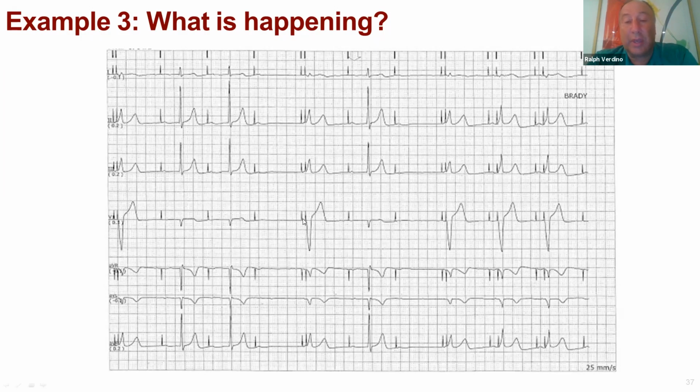So it does 2 things by doing that. Number 1, it shows you that it did sense that there was no beat in the ventricle before it. It's not over sensing, okay? But what it did is it said, I want to show you that I'm in MVP mode by giving a sub-physiologic AV interval on the beat after the drop beat.